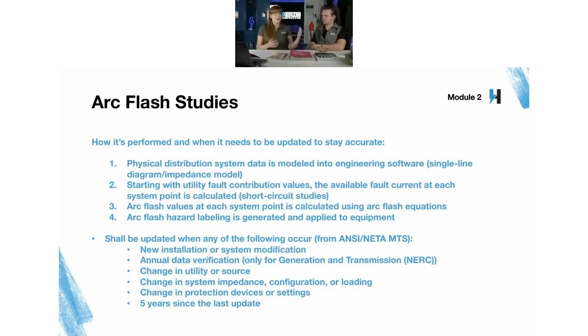If there's been an update in your system, a setting change, a fuse change, you've rerun equipment to something else, or you've sized up or sized down your conductors, there's all sorts of things that could cause a pretty big change in the results of your arc flash study. And so anytime that happens, from the point of that change downstream, the rest of that section of the one line, you really shouldn't be looking at those labels anymore until you verify that they're still accurate or get them replaced. Oftentimes, a couple of them will need to get replaced or more.